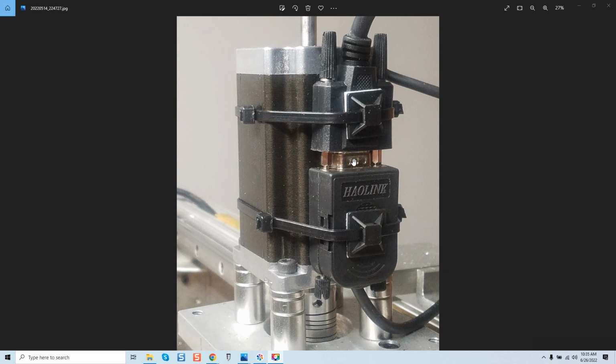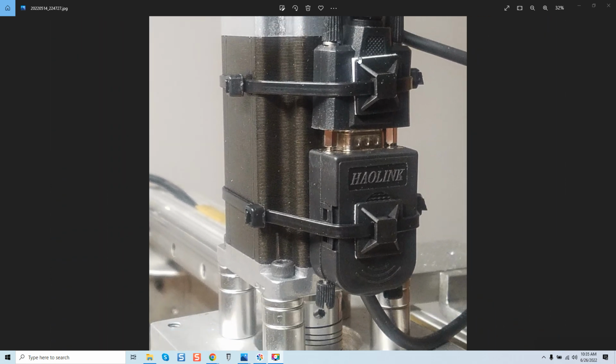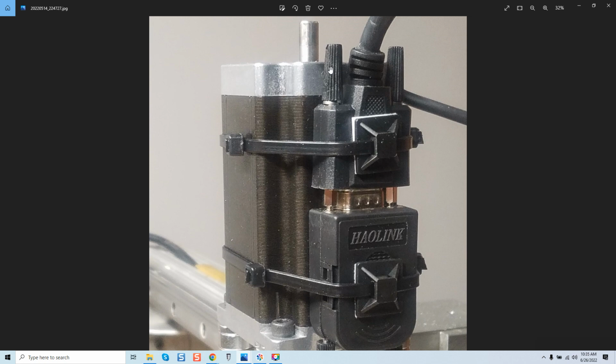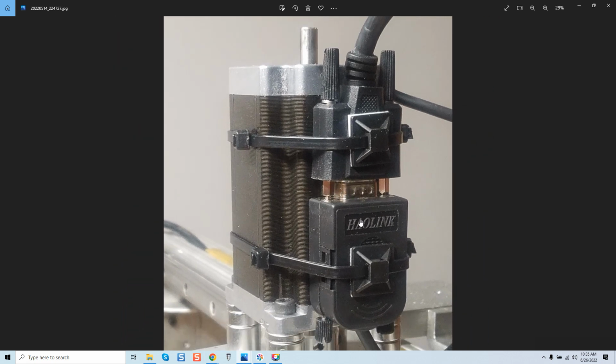The other thing I want to point out, and this is something a lot of guys don't even think about, is that a DB9 connector or any connector for a motor, whether it be GX16, DB9, whatever it may be, when you screw these connectors together, and you can see these jack nuts right here, one, two, and of course how those jack nuts are actually screwed into is from these top screws on this DB9 cable. What you're doing is essentially formulating a joint. The issue is that vibration, when it's transferred from your chassis to those joints, eventually has a lot of potential.